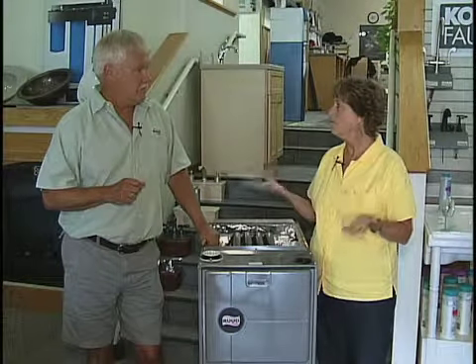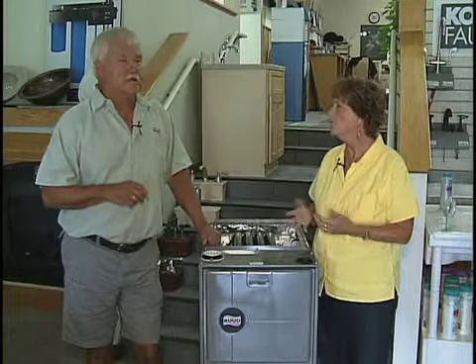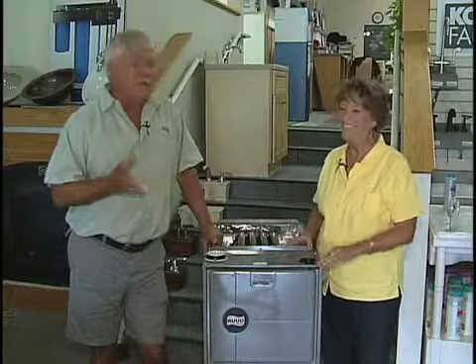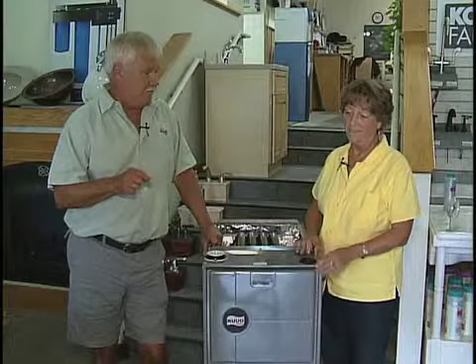Yeah, and I don't know if our viewers have heard about these new motors. There's a lot of buzz about it because there are rebates available, and they're called ECM motors. And what does that stand for? That stands for electronically commutated motor. I don't know if that means anything to you. What it means is it's kind of a variable speed motor. And because it doesn't run at full capacity all the time, it ramps up to the speed it needs to be, and it ramps down again when it's done, and it uses way less power than a normal motor does.